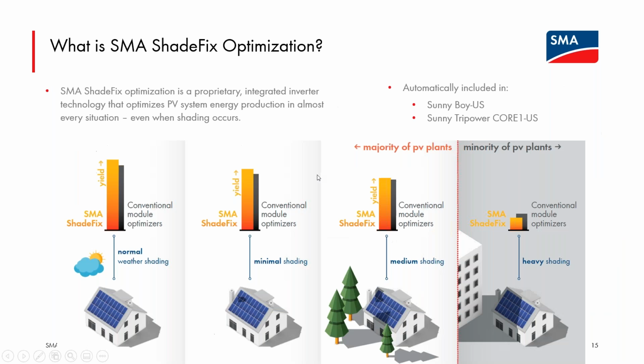So the array is broken up according to those tracking channels for purposes of the CORE1 applying this ShadeFix algorithm. And this graphic is coming from a white paper on ShadeFix that is on the SMA-America.com website. I think this is a really good piece of information if you're discussing with a potential system owner what ShadeFix is providing. The takeaway from this series of graphics is, in comparison to a standard DC optimizer system, an SMA ShadeFix optimized inverter is capable of providing higher yield, that is AC kilowatt hours out of the inverter, the only metric that pays off the system and makes the system owner money.